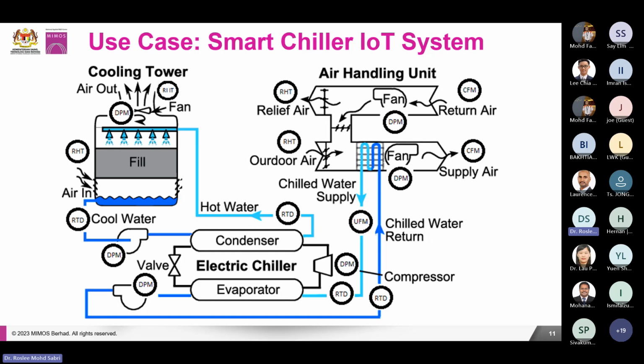In order to introduce IoT to an HVAC system or a chiller, you need to add a lot of sensors. Basically you're going to have things like temperature and humidity sensors to measure the indoor and outdoor temperature to get a view of the heat load. You also need a power meter to measure the electrical consumption of the compressor, the water pumps, the fans, and all the electrical equipment.